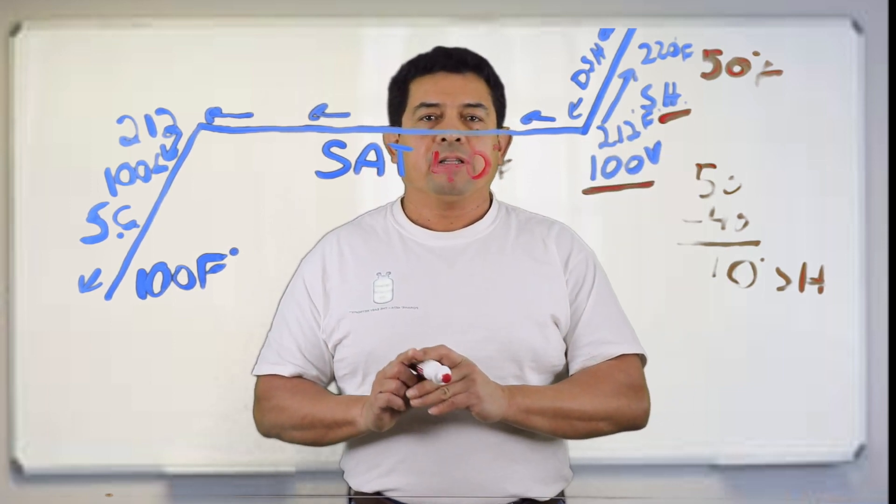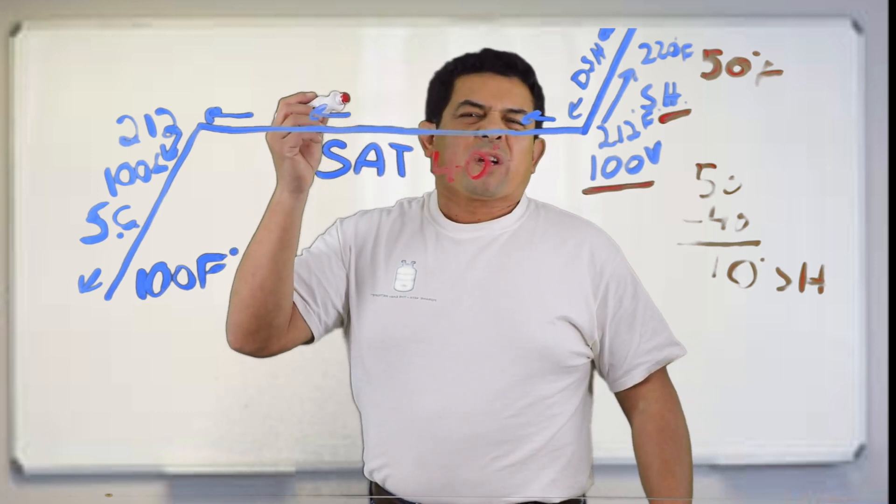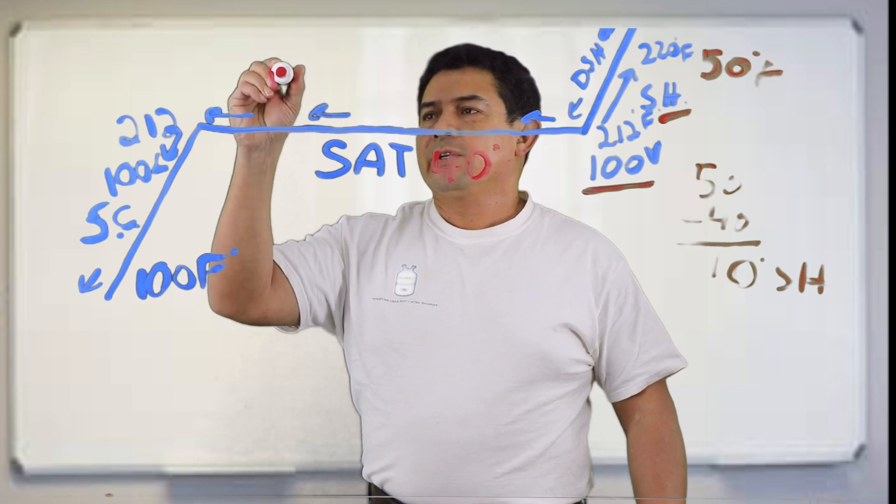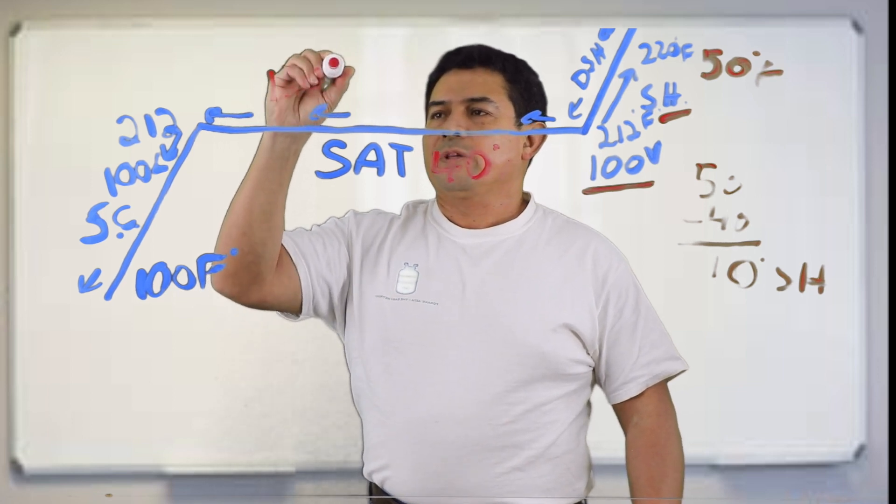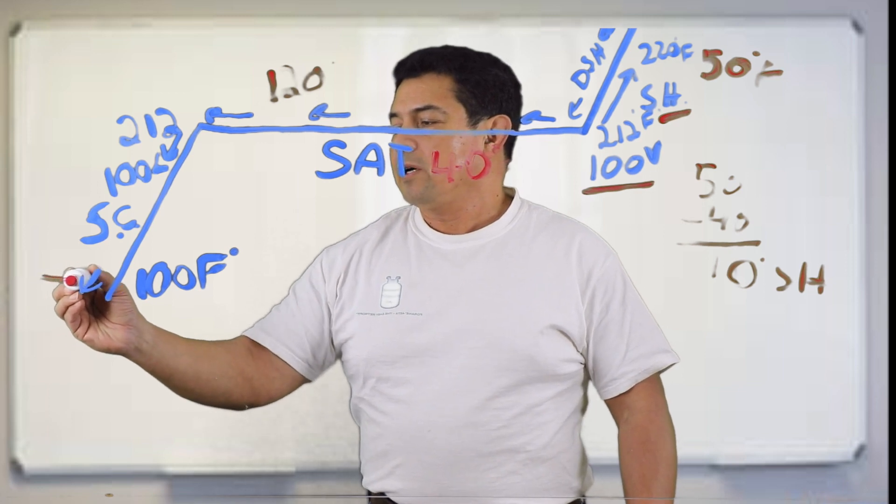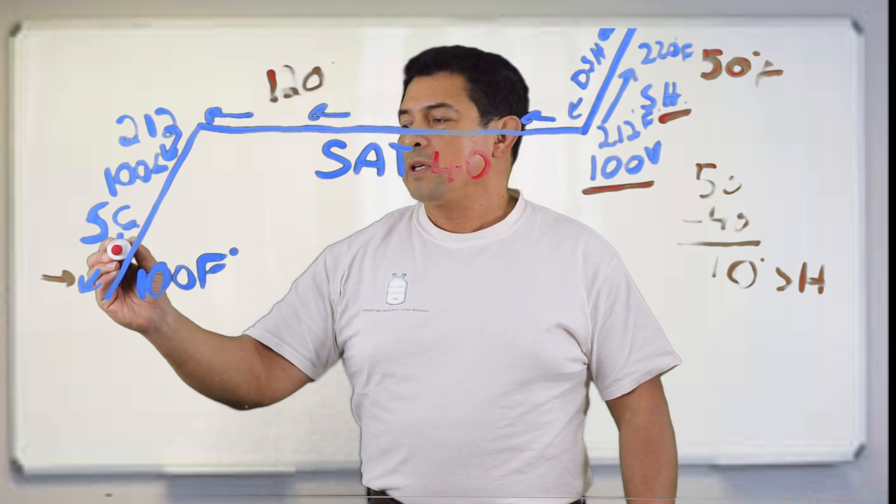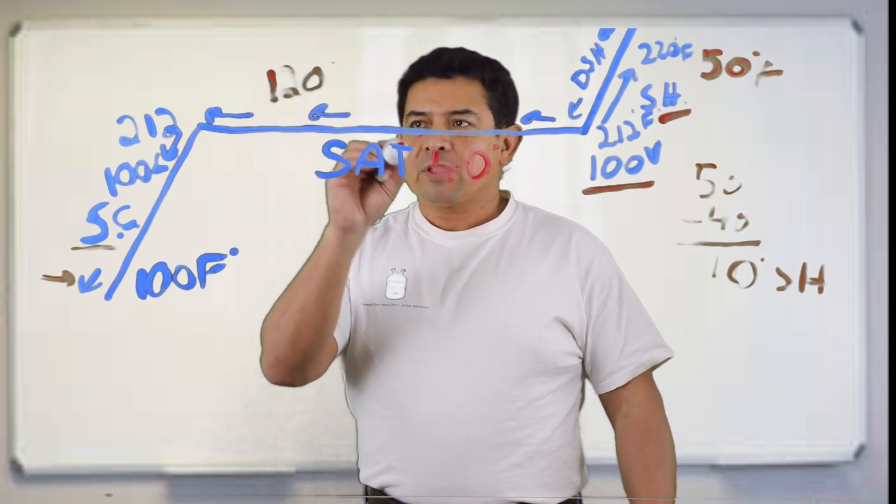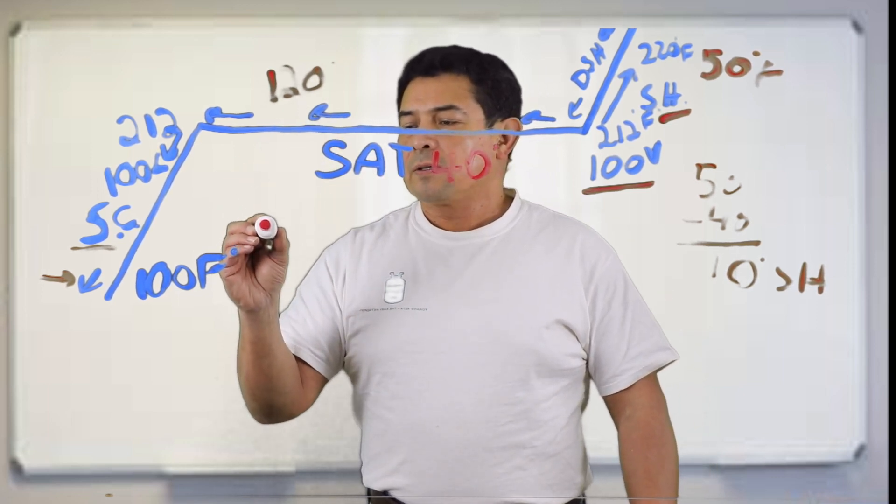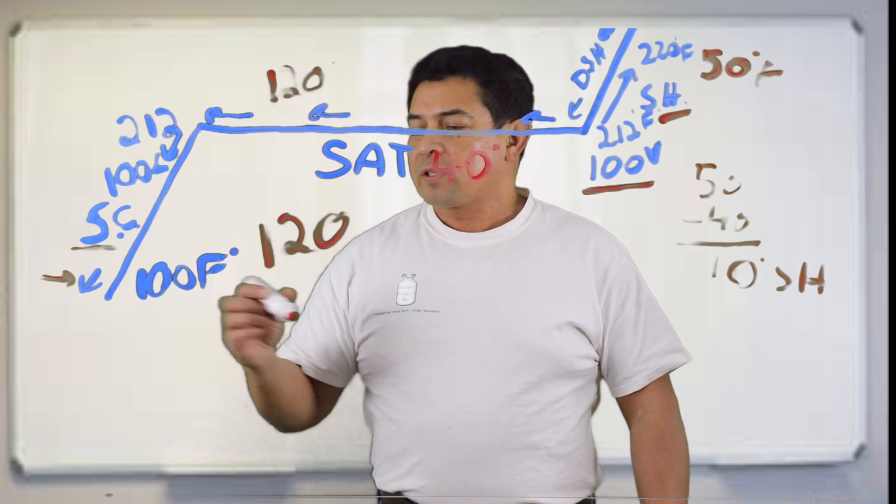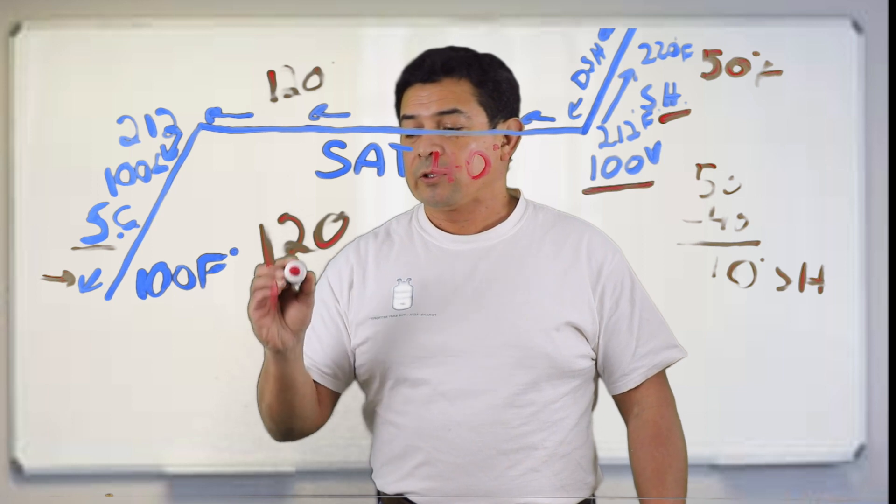On the other hand, if we think about refrigerant, let's say we're condensing the refrigerant in the condenser at 120 degrees. We lower the temperature down to 100. So we subcooled. The saturation temperature in the condenser is going to be 120 degrees. We subcooled, or we lowered the temperature down to 100.